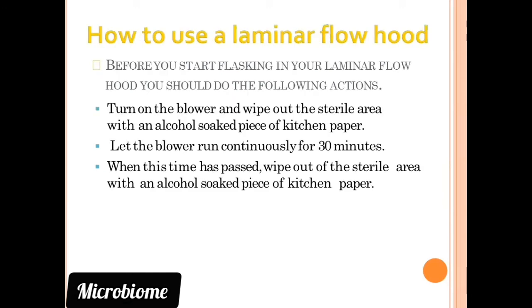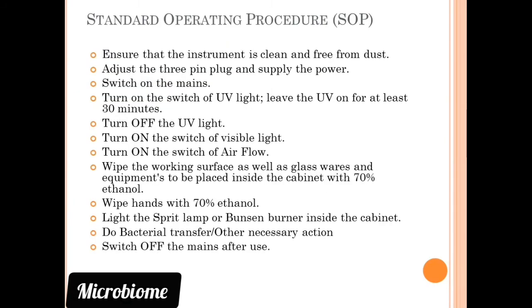Then how to use a laminar airflow hood? These are some standard operating procedures. First, ensure that the instrument is clean and free from dust. Second, adjust the 3-pin plug and supply the power. Then switch on the mains. Turn on the UV light. Leave the UV on for at least 30 minutes if possible. Otherwise, you can switch it on for 15 minutes also. Then turn off the UV light.